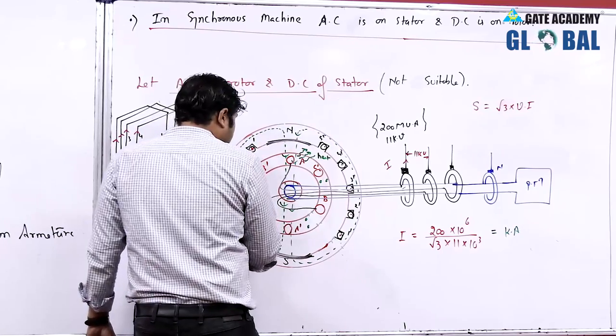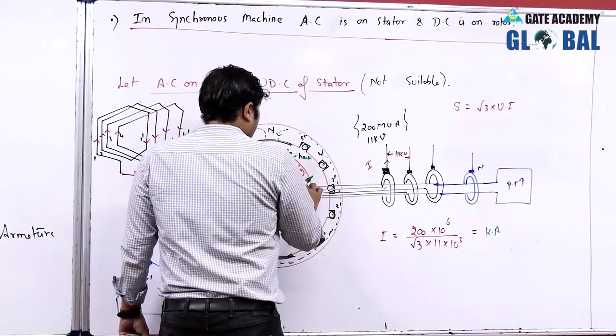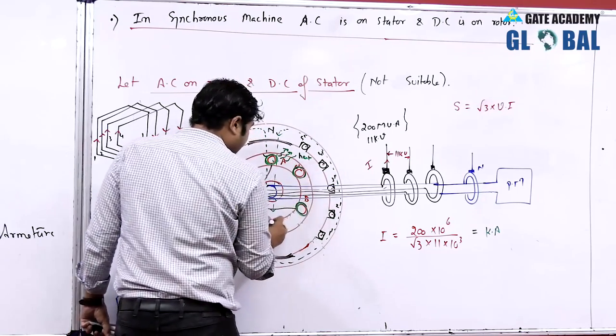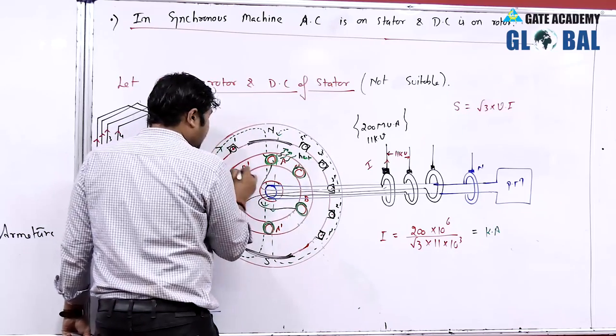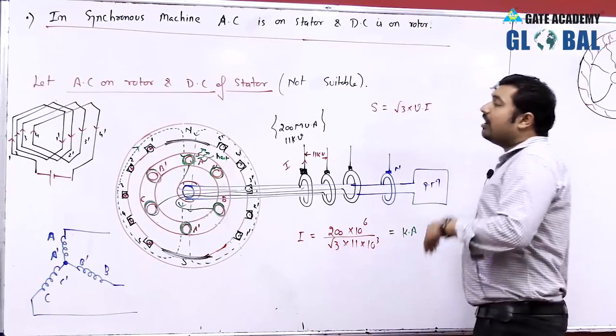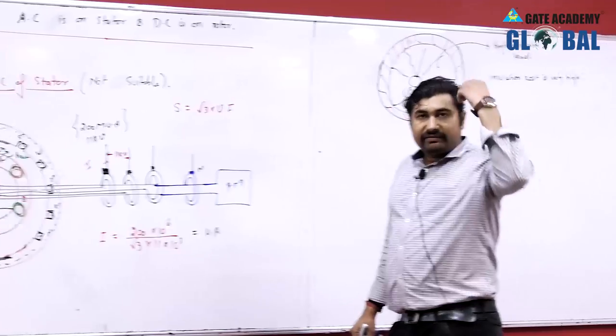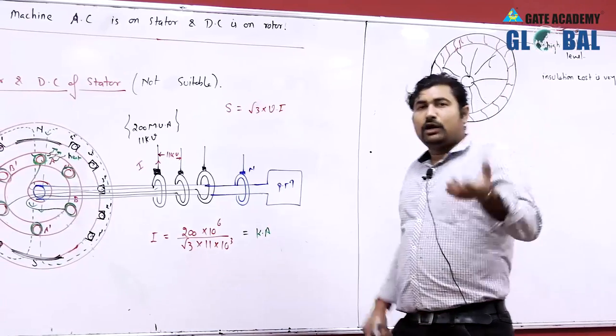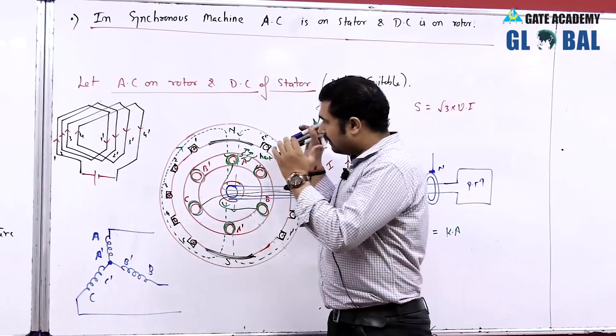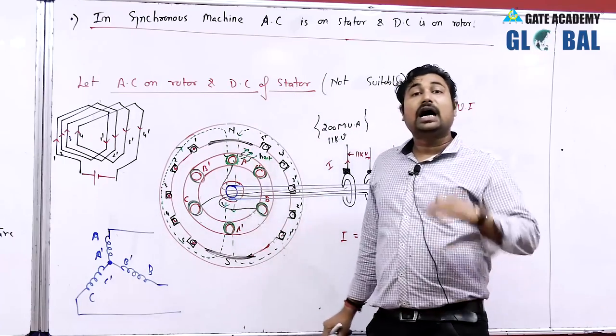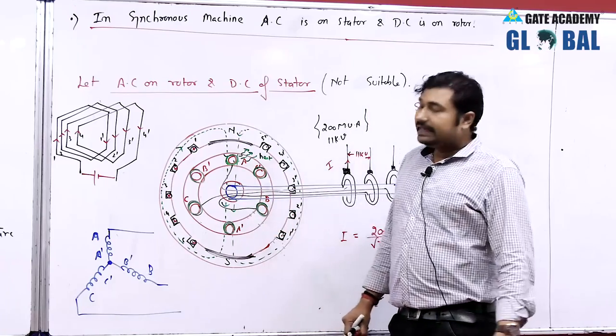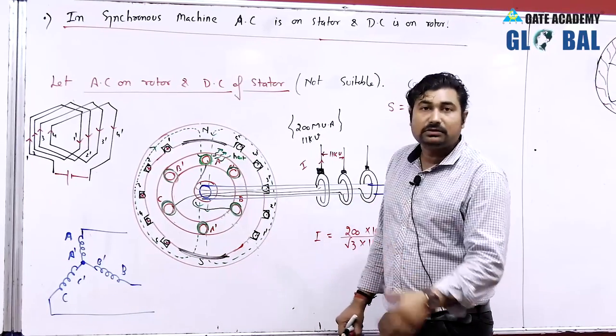Centrifugal force needs a very large cost to hold the conductors. Insulation cost for the slip rings is very high. Frequent maintenance is required. Even if we had enough money to handle centrifugal force and high insulation cost, effective cooling is still not possible if AC is on the rotor and DC is on the stator field. That is why we never prefer large synchronous generators to be designed with AC on the rotor and DC on the stator.